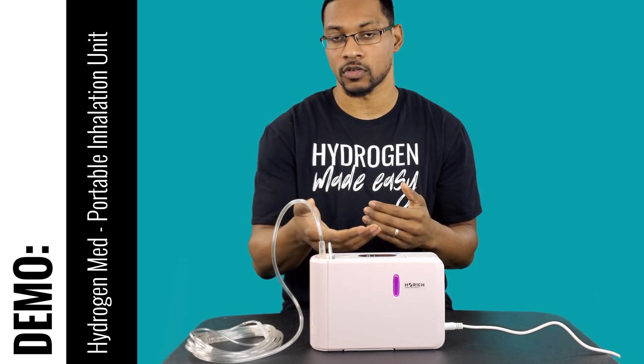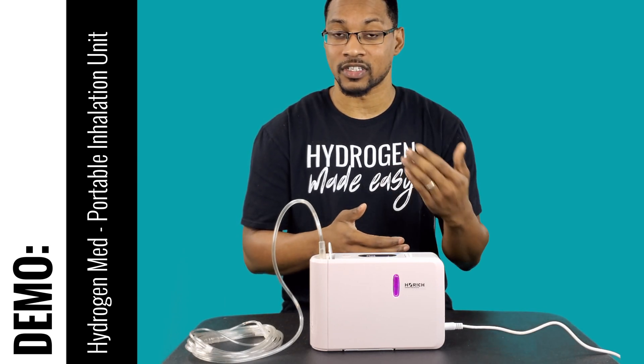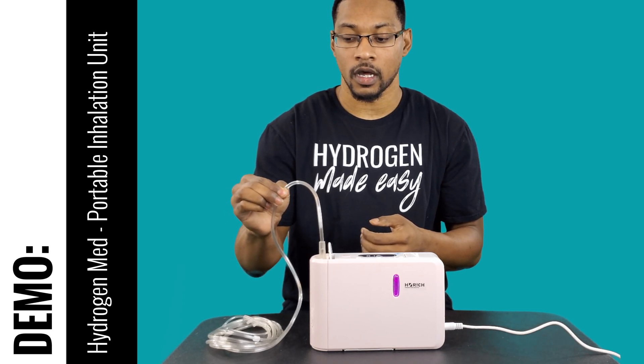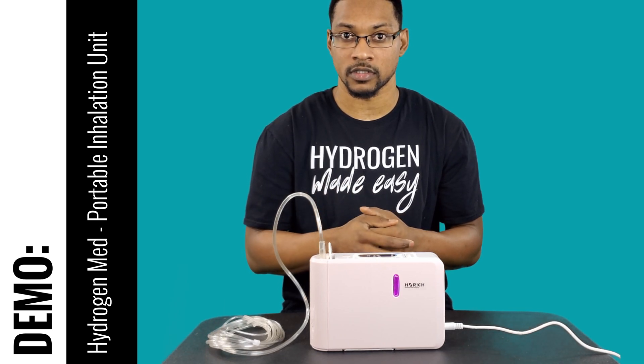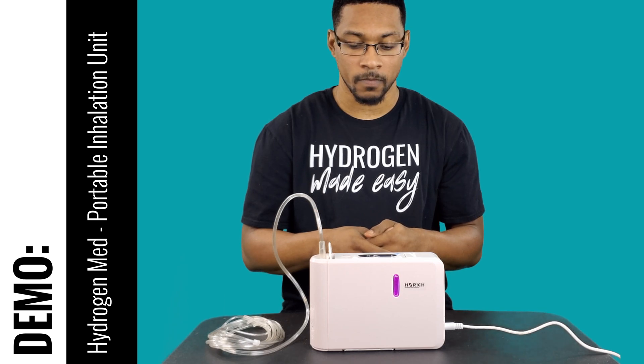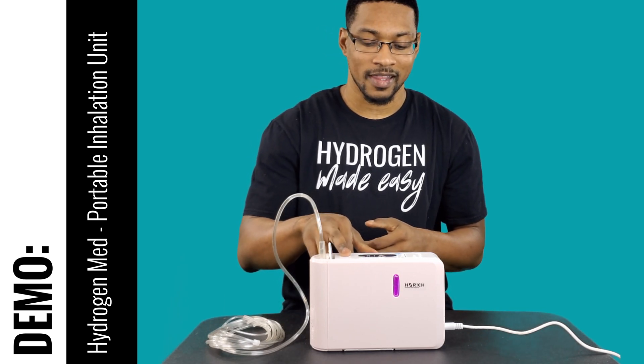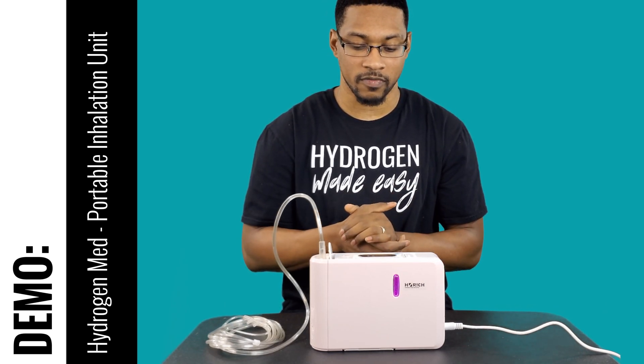There's another safety feature where if the line gets blocked, it'll give you an error signal — you don't want any buildup of hydrogen gas. Those are just a few of the functionality safeties of the system. Overall it's just an on/off switch — a very simplistic device.